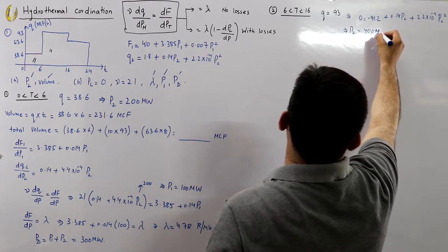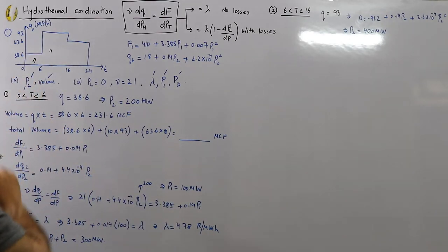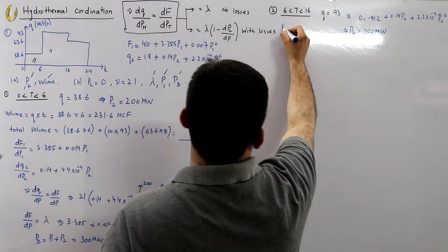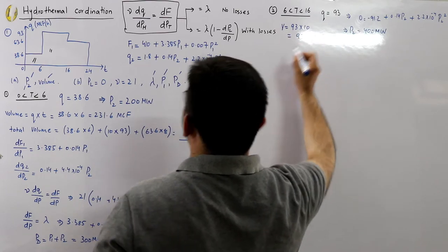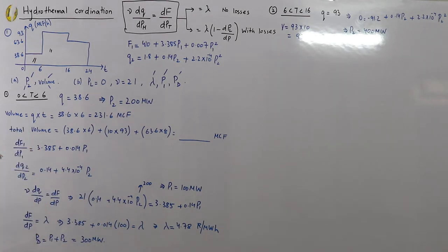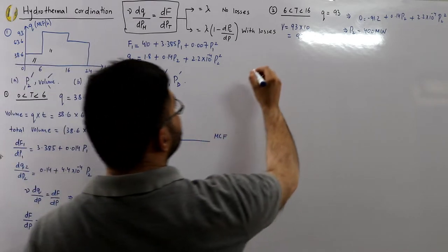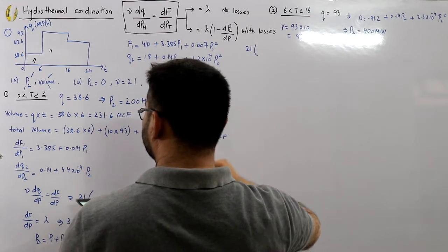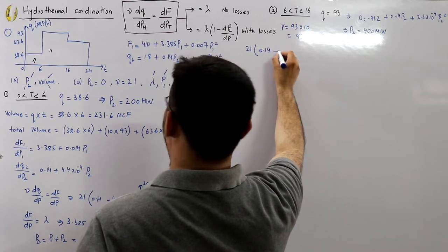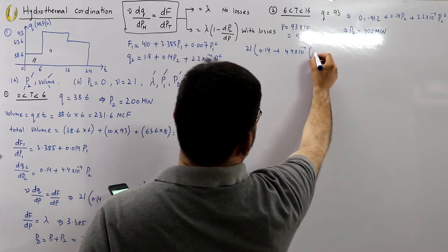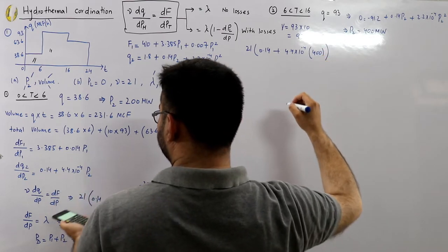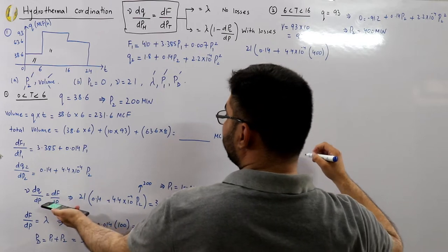The volume used in Interval 2 is V = Q × t = 93 × 10 = 930 million cubic feet. Applying the coordination equation again with ν = 21 and P2 = 400: 21 × (0.14 + 4.4×10⁻⁴ × 400) = 3.385 + 0.014·P1.